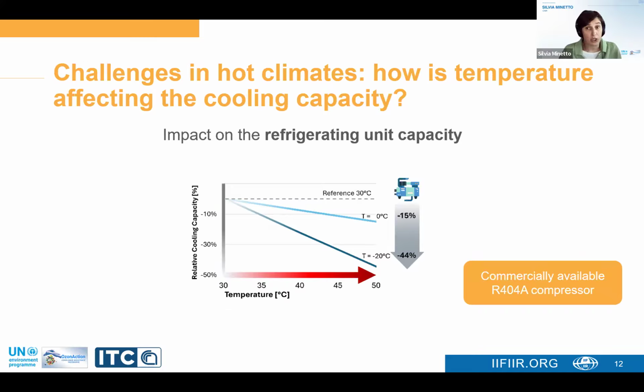And if the temperature outside increases, then the cooling capacity that the compressor and the refrigerating unit itself is going to deliver is much lower. This graph is just a trend, and it represents what happens to the cooling capacity of a compressor. We selected a commercially available R404A compressor from a manufacturer catalog. The cooling capacity moving from 30 to 50 goes down by 44% if we work at -20. Of course, these numbers are related to the compressor that we have selected, but the trend is very similar for all compressors and refrigerants.